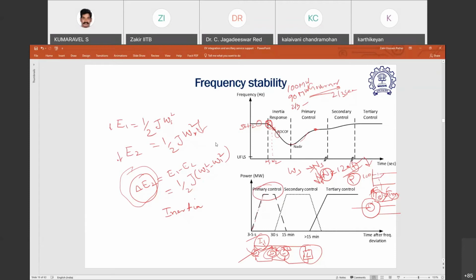Same is true here. We have the primary frequency controller, which is automatic, but it's a controller. It is a manual controller in the sense that it is actually introduced as a supplementary controller in the machines. It is not inherent. So this primary frequency controller needs active power to control it. That active power should be there, and that active power available is known as reserve. It is a backup power which should be available with the generator.